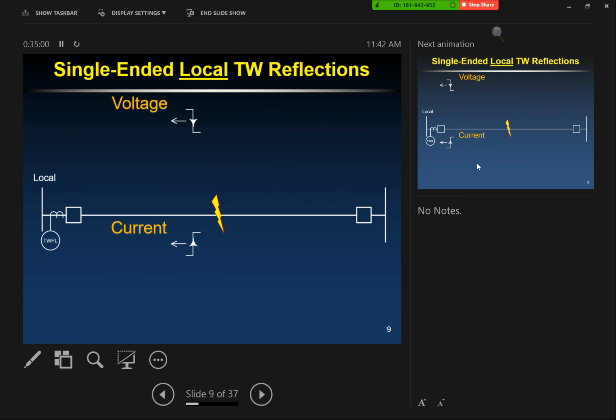Get a fault on the line. We will get traveling wave voltage and current flowing back toward the local terminal. What polarities do we expect for these? I'm showing these correctly, but do these make sense? We get a negative voltage, it's a depression in the waveform, right? We're collapsing the voltage at the point of the fault. So you expect that negative voltage polarity to travel back. It's also going to have a negative voltage polarity traveling to the remote end.